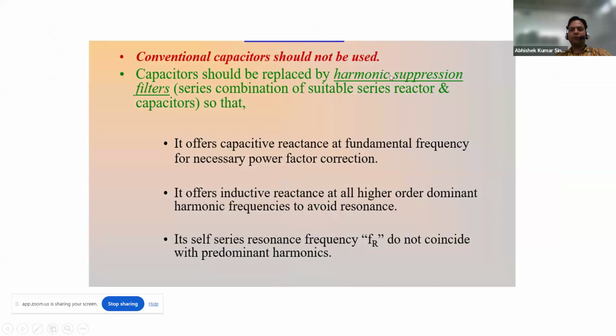So what is the filter doing? The filter is suppressing the harmonics. We need to understand that it is suppressing the harmonics, it is not killing the harmonics. Only an active filter can kill the harmonics, but a reactor cannot kill the harmonics. A reactor can only suppress the harmonics. So this is a very important difference between these two.